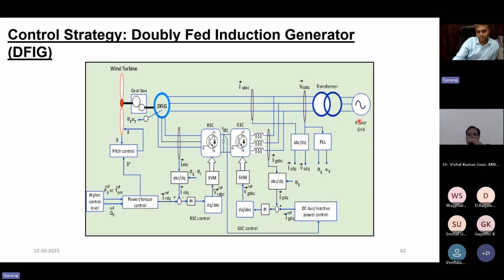Now, please understand, in steady state operation, the flux which is present is synchronized with the time variation of the voltage. So it's a time varying flux, right? There is no DC there. The rotor is rotating close to synchronous speed, and the relative speed variation is very small, so the voltage being induced on the rotor side is very minimal. Whereas whenever there is a transient event, there is a DC component of flux which is also seen in addition to the AC component of flux, which is steady state.